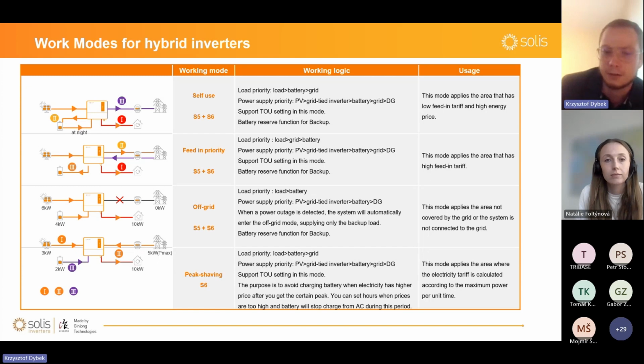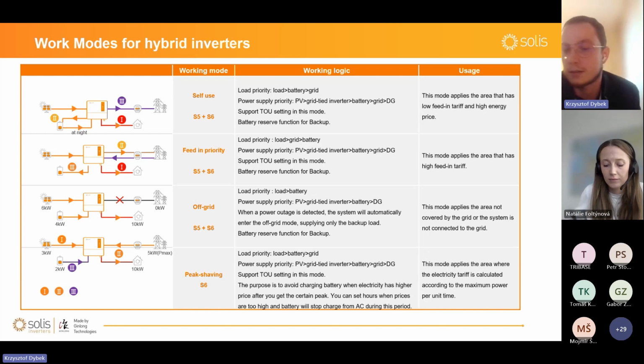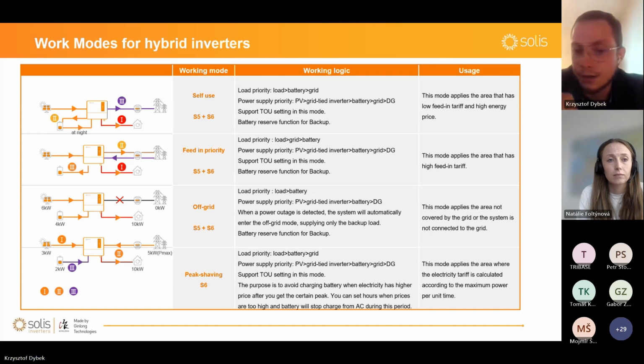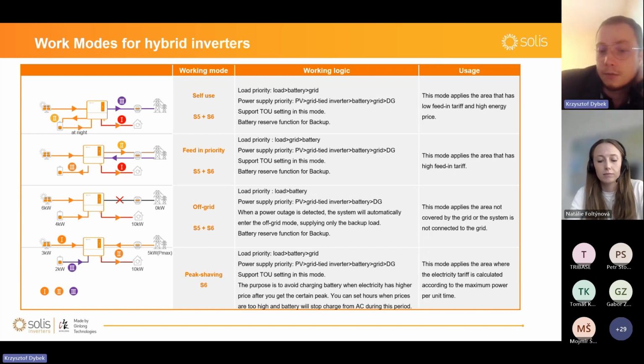And yeah, about peak shaving. The purpose of it is to avoid charging the battery when electricity has a higher price after you get a certain peak. So you can set hours when prices are too high, and the battery will stop charging from AC during this period. In bigger commercial inverters, peak shaving mode is also applicable when you want to use a generator or third-party inverter on site. So the battery will charge from AC only until a certain peak level, and after that, let the generator charge it instead of using AC from the grid.